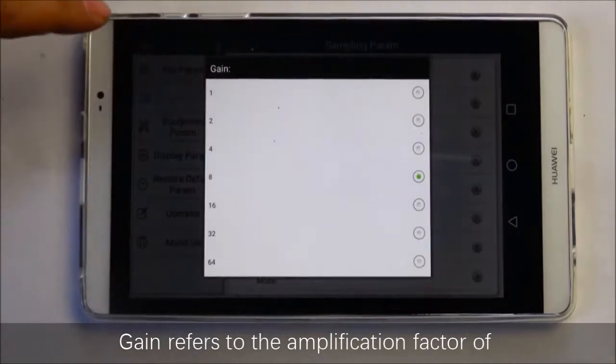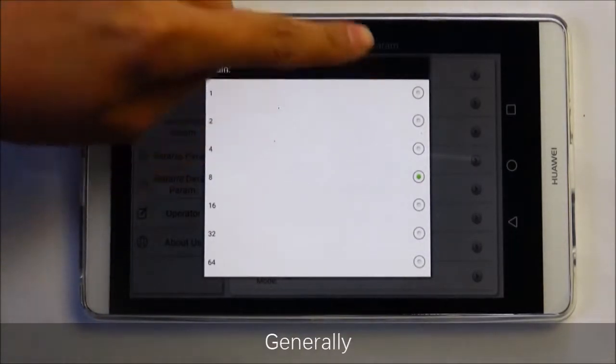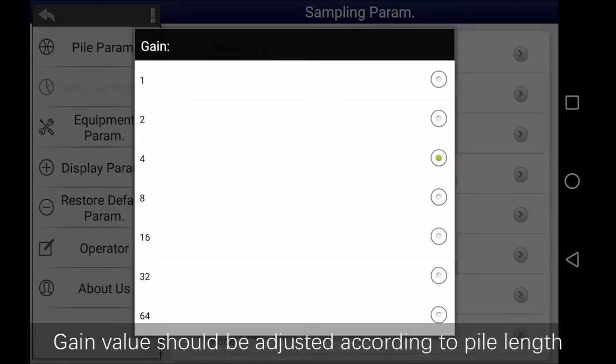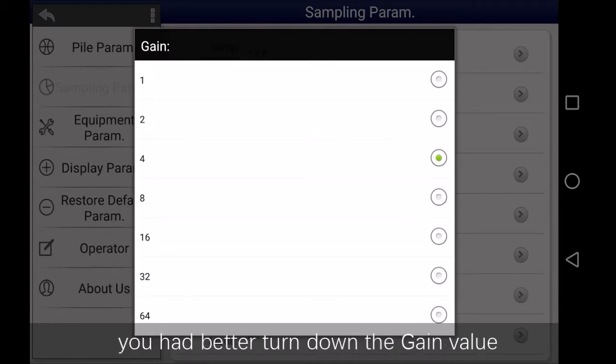Gain refers to the amplification factor of the signal received by the sensor. Generally, the gain value should be adjusted according to pile length, condition of the pile head surface, and striking equipment. When the signal is weak, you can turn up the gain value. When the signal is strong, you'd better turn down the gain value.